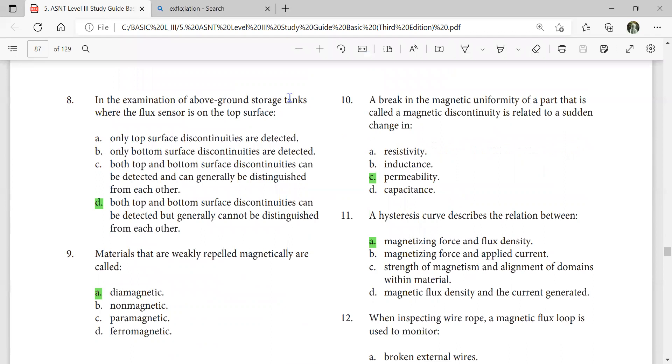In the examination of above-ground storage tanks where the flux sensor is on the top surface, both top and bottom surface discontinuities can be detected but generally cannot be distinguished from each other.